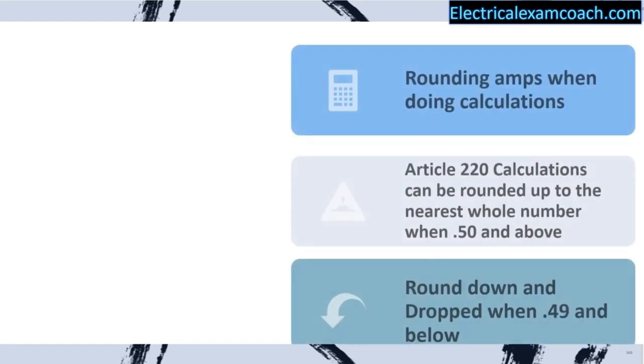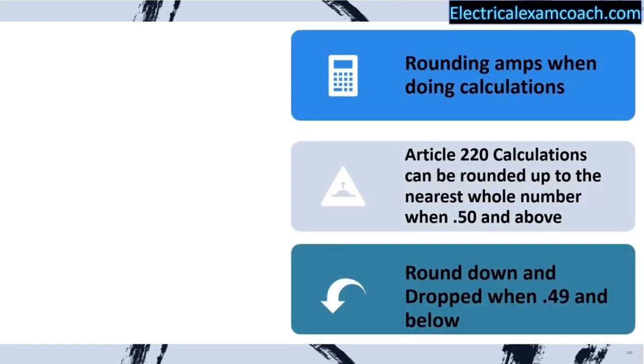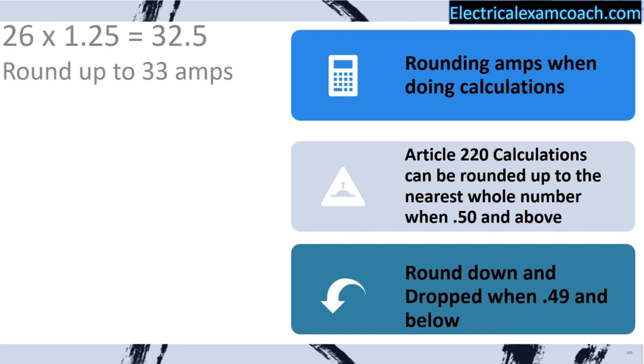In Article 220 calculations, we're going to be able to round up or down. We're going to round up to the nearest whole number when it's 0.50 and above, and round down when it's 0.49 or below. We're only going to do it one time at the end of the calculation — you're not going to be rounding in between each piece, or you'll end up with the wrong answer.